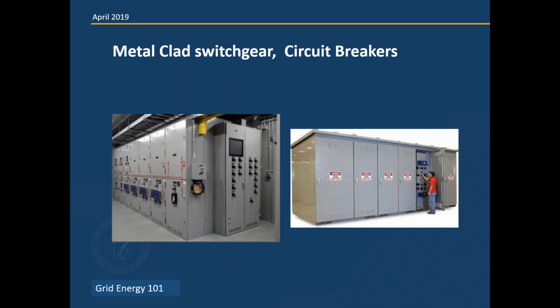So here's a typical example of metal-clad switchgear circuit breakers. Inside these cabinets are circuit breakers that will be racked in, racked out, closed. A lot of the times when folks are dealing with these things, they're indoors and they require special personal protective equipment and face shields, because if there's a fault in there, it's going to blow out through the door. They're a very versatile piece of equipment, but they have special challenges when operating. Next slide, please.